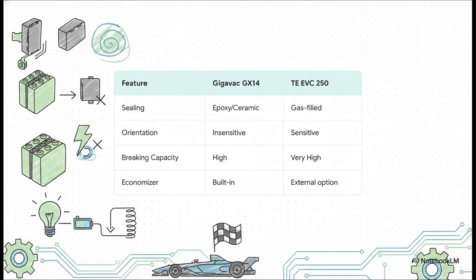Now, the main contactors, those AIRs, are the big gatekeepers for all that high-voltage power, and which ones you choose is a huge design decision. For instance, a Gigavac GX14 contactor uses an epoxy seal, which means you can mount it in any orientation you want, a massive advantage when packaging everything into a tiny battery box.